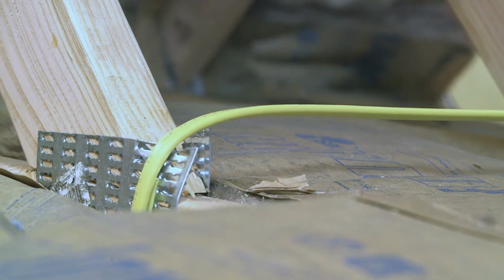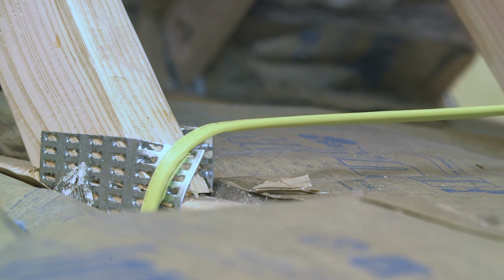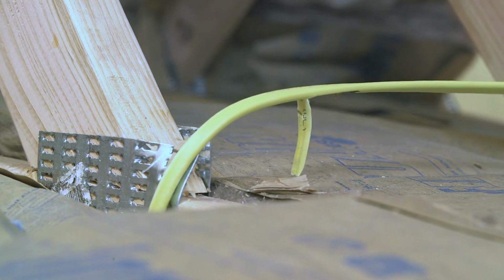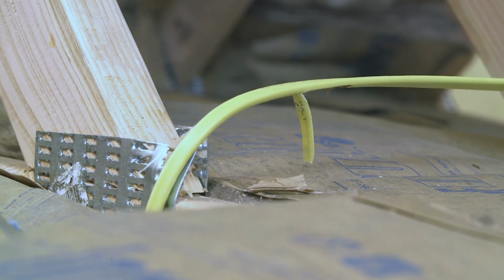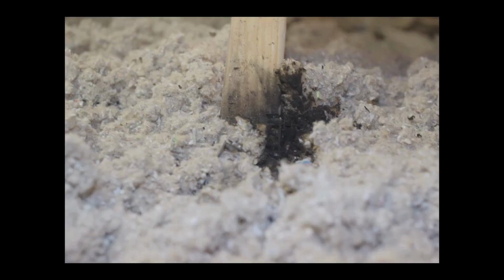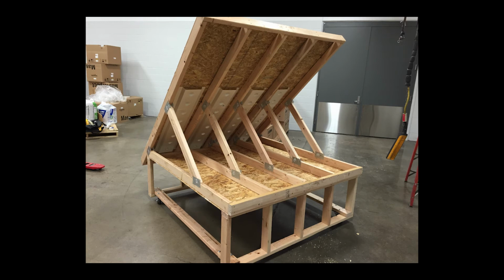When NM cable is pulled through an attic, occasionally it may rub against a roof truss gusset plate, damaging the cable insulation. Many times the damage is invisible to the electrician as they're pulling the wire through and they may miss the damage. It may take a long time for the damage to result in a dangerous arcing condition. We use the same arrangement of an AFCI breaker in the panel with an AFCI receptacle in the first outlet box and a second test with the standard circuit breaker in the panel.